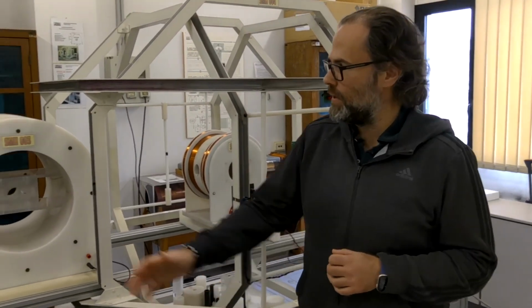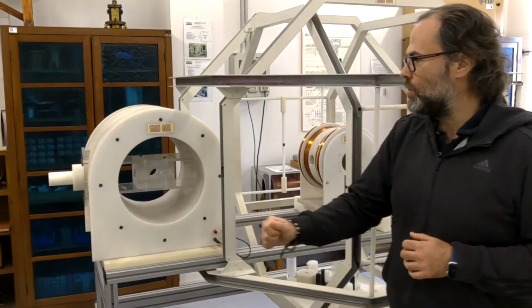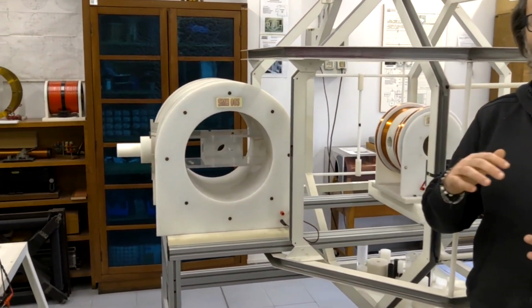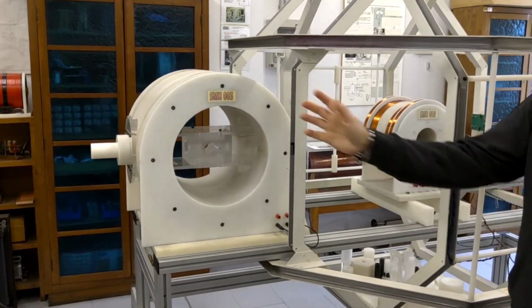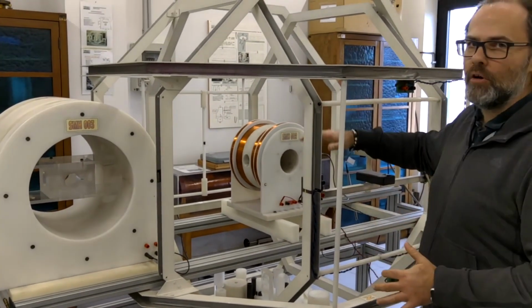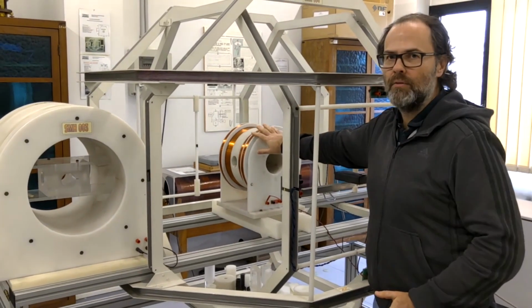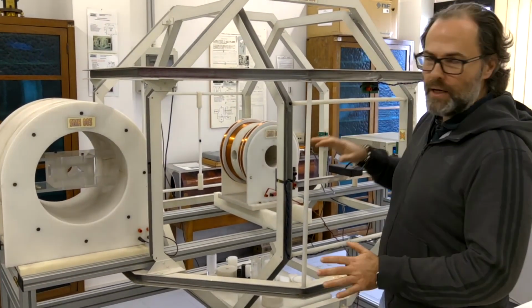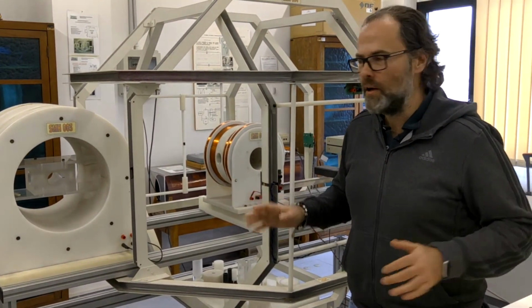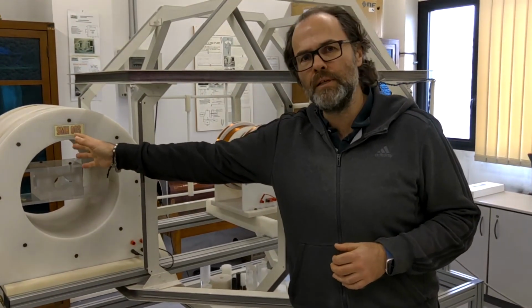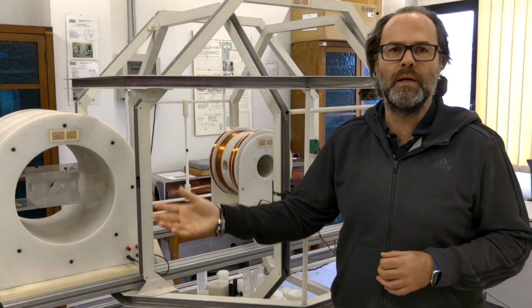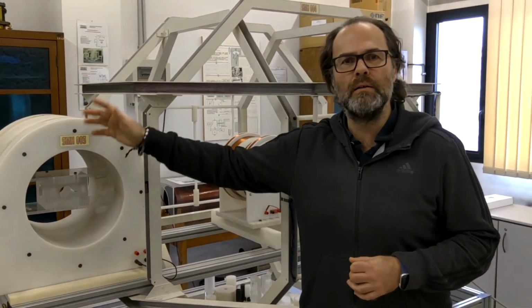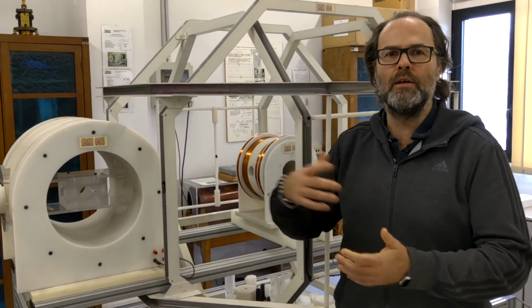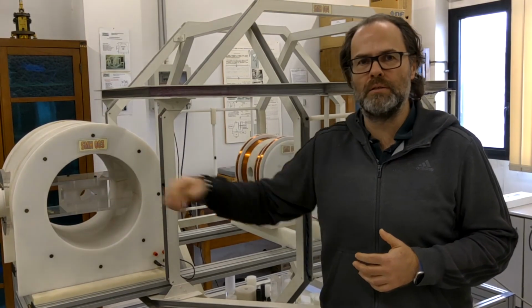In case we want to calibrate a probe at even lower intensities of applied magnetic field, we have another set of coils whose range is between 15 microtesla and 1 millitesla that can be placed in the middle of the Helmholtz coils that compensate the Earth magnetic field in place of the ones that we used today. For the rest, the procedure is exactly the same. Of course, the calibration constant of these coils is different, but is again obtained through the nuclear magnetic resonance experiment in order to calculate the coefficient linking the current to the magnetic field generated by these coils.